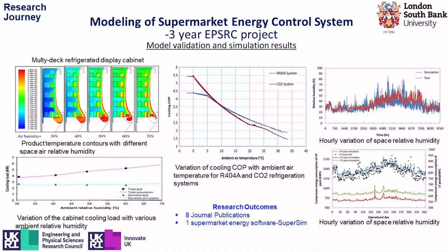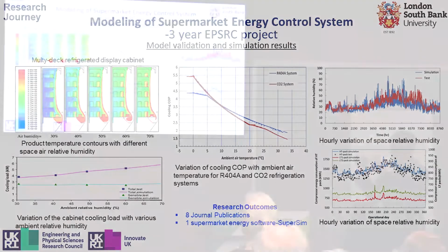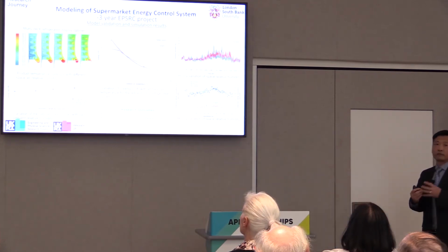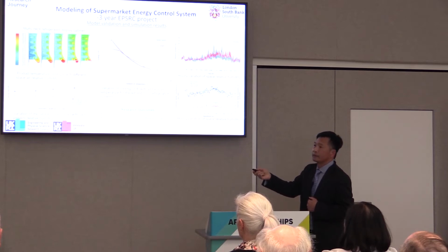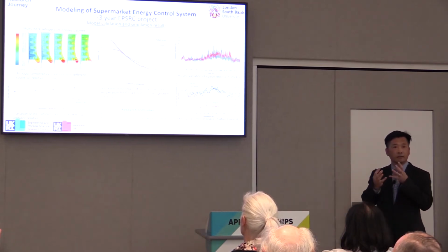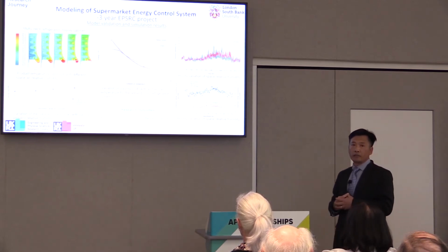You can see the food temperature change with the room space relative humidity here. From the top left diagram, when the indoor space relative humidity increases, the food temperature inside the cabinet gradually increases. That means when you increase the indoor relative humidity, the cabinet refrigeration load will increase, as shown in the bottom diagram, and it increases linearly. From this simulation result, we can obtain the functions of R listed in the last slide. Then we integrate it into our whole supermarket refrigeration system model, so we can accurately predict the performance of the refrigeration system.